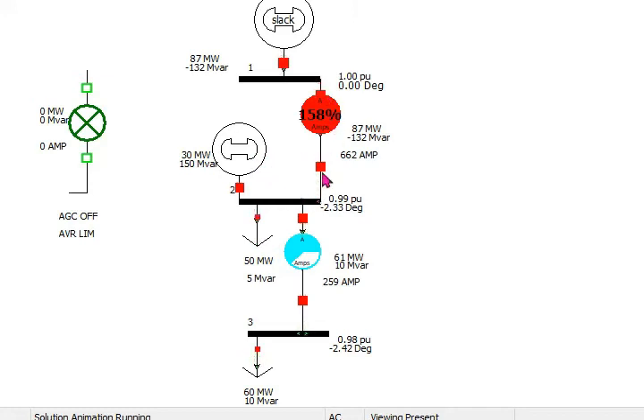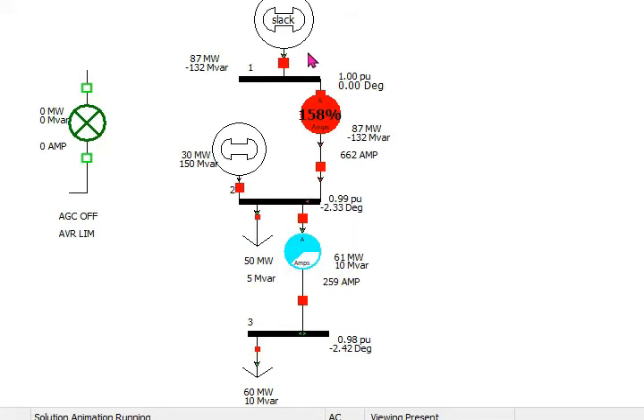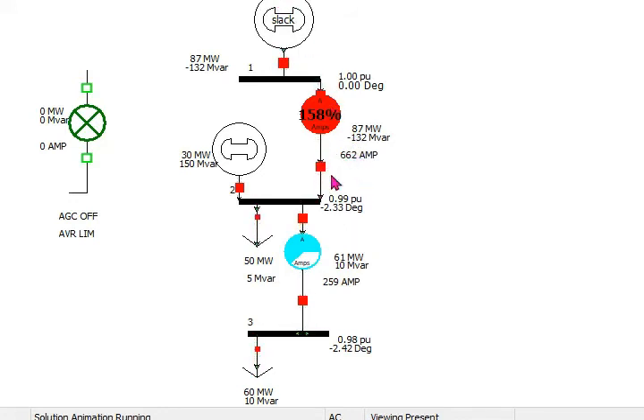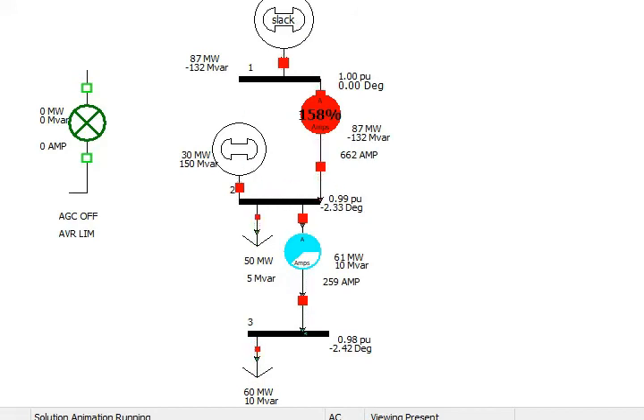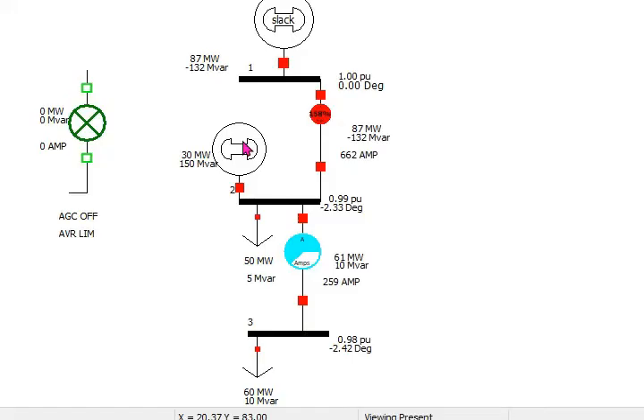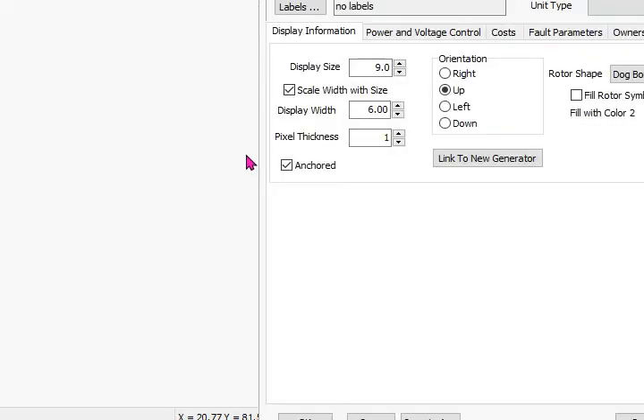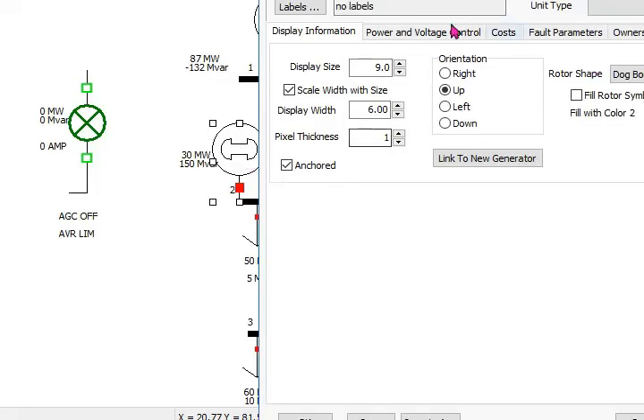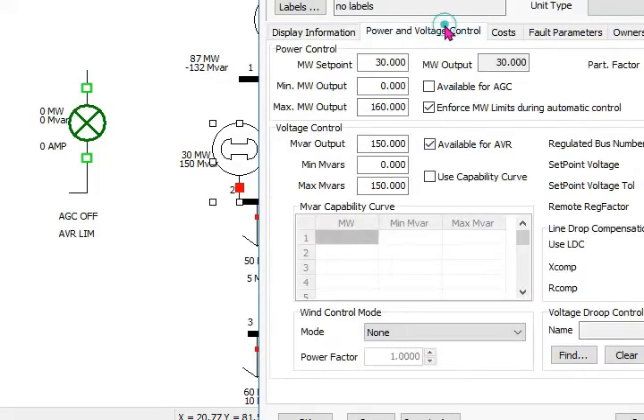So 150 megavar is generated by this generator. This generator tries to generate maximum available reactive power, that's 150 megavar, back to this line, and the voltage maintained by this is 0.99. So this generator was unable to maintain, it tried a lot, it's trying to maintain.